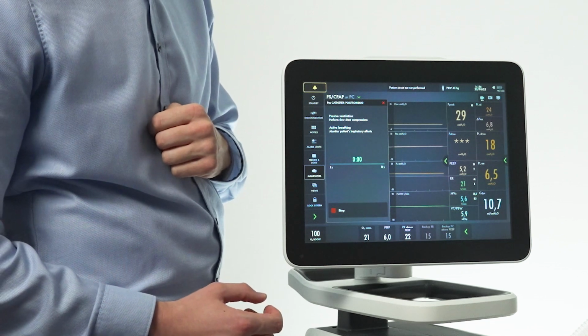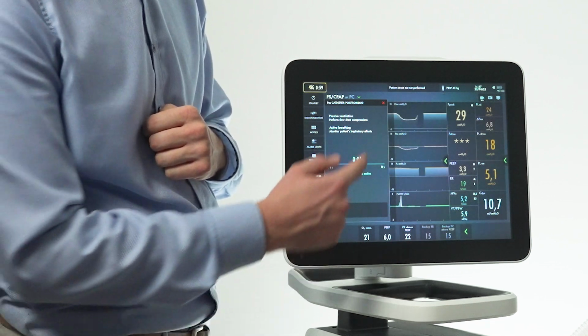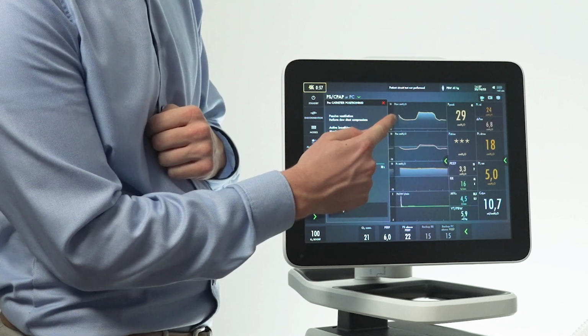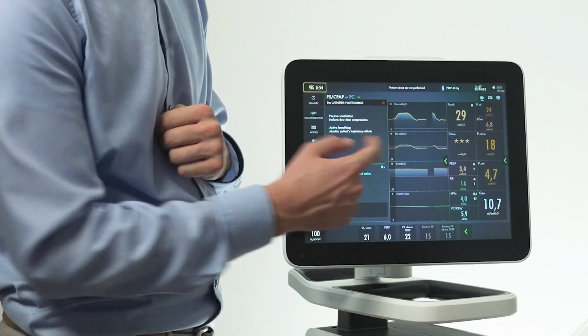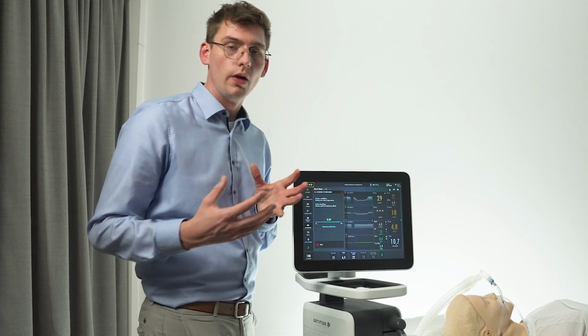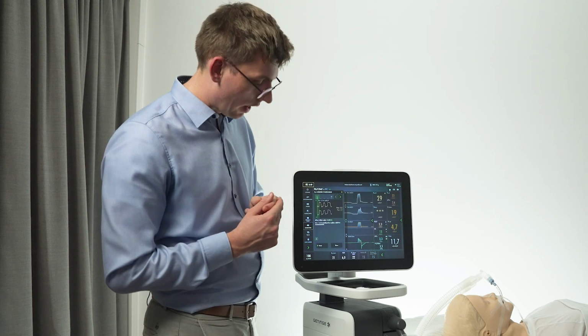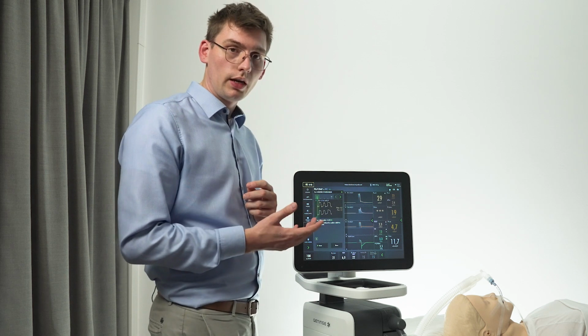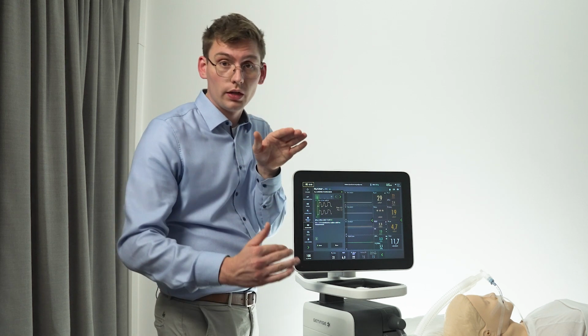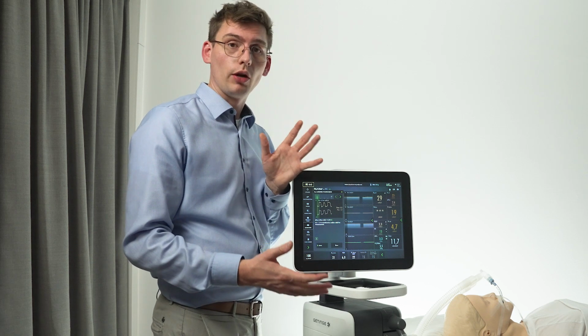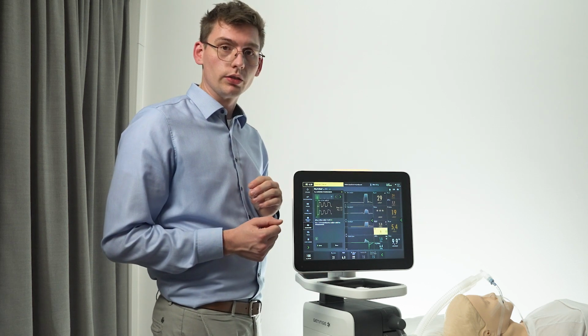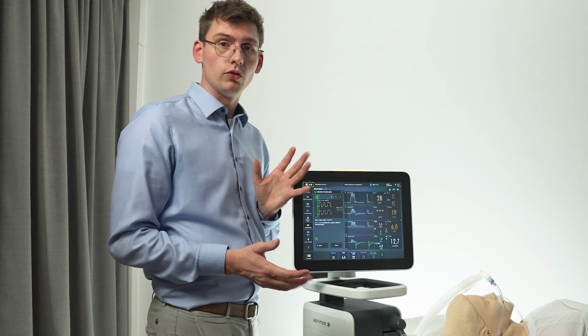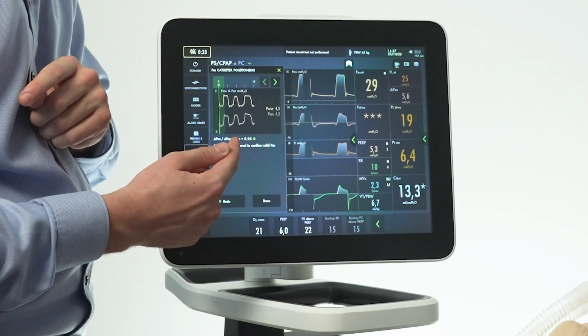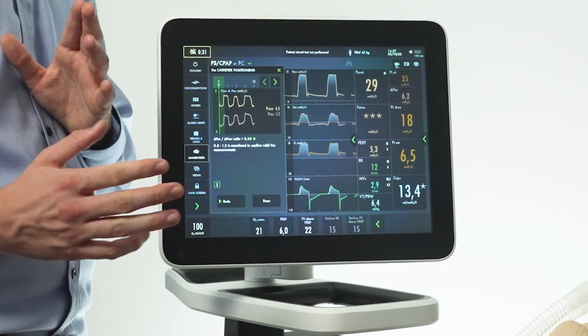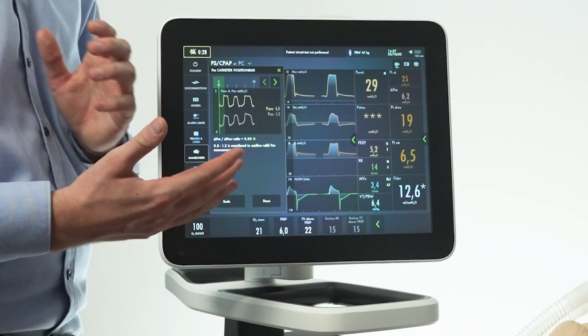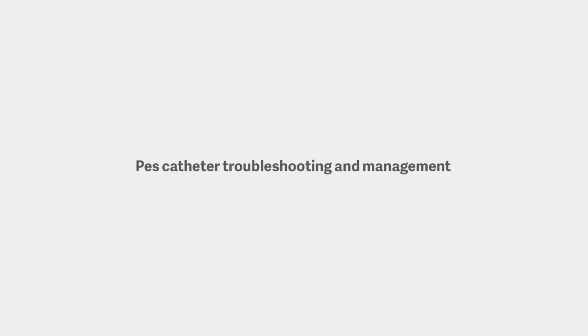And now when our patient is trying to inspire, you can see that airway pressure is going down and esophageal pressure is going down as well because the patient is trying to inspire against a closed airway. And once again, the tool will automatically give us the ratio between the drop in esophageal pressure and the drop in airway pressure. And we want the same ratios here, so between 0.8 and 1.2. And as we can see here, the ratio in this specific patient is 0.95, which is very good and means we can trust these measurements to make our assessments of the patient.